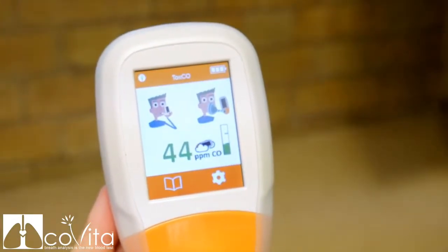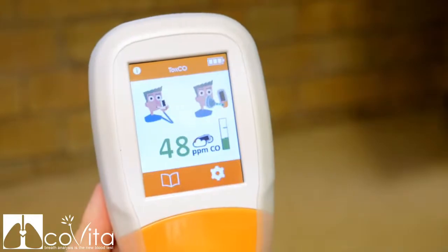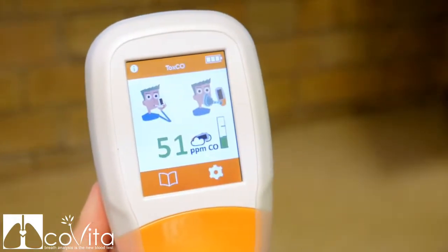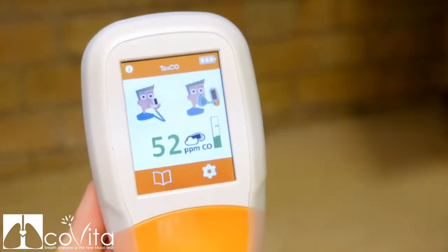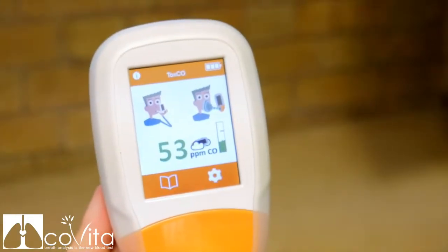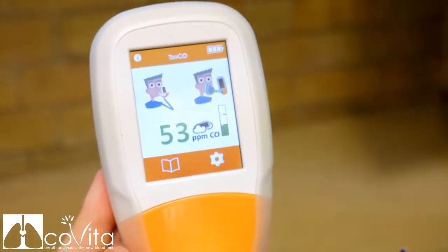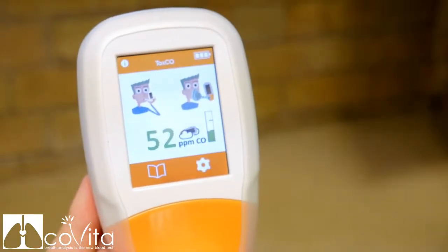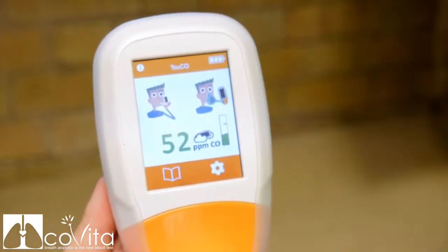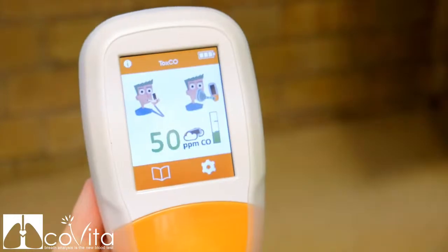When a CO threshold is breached, the monitor will log this event and continue to log the live reading every minute. The logging will continue for 8 hours or until the monitor is switched off. You can access the log by clicking on the history icon and selecting the ambient log.